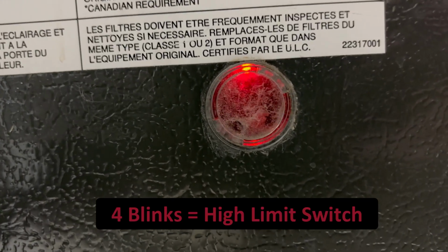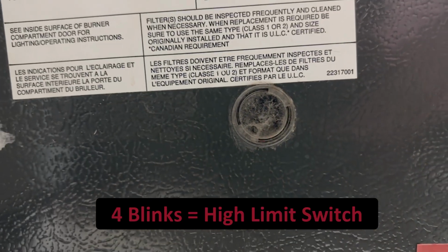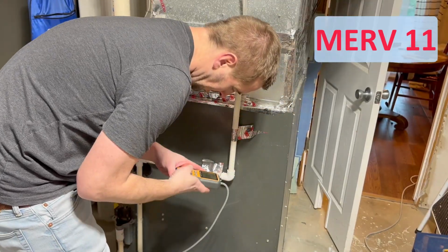So kind of interesting, going from the MERV 8 to the MERV 11, pretty much right away our temperature limit switch tripped on the furnace. So that shut down the heating, fan had to run for about 5 minutes to cool the system off. And what that tells me is after even just the MERV 8, it was kind of pushing our system to the limits as far as airflow and being able to circulate enough air to keep that temperature from rising to the limit. So I think with our system, there's definitely some other aspects that are hindering performance. That said, let's get back to testing this MERV 11.